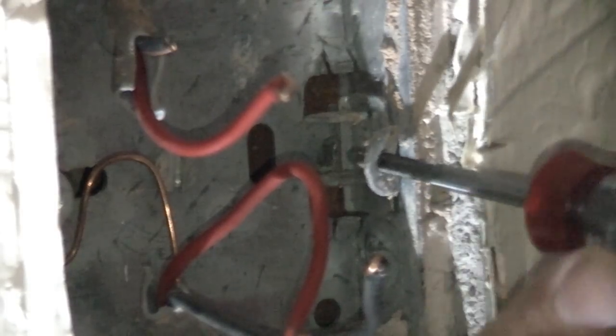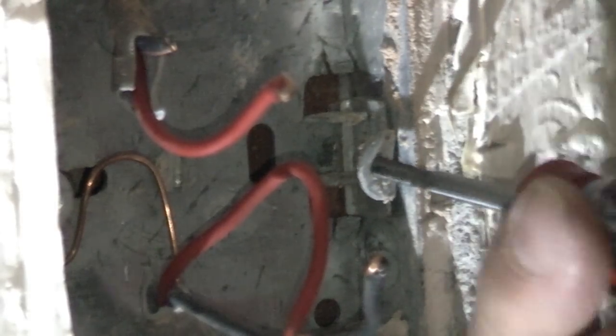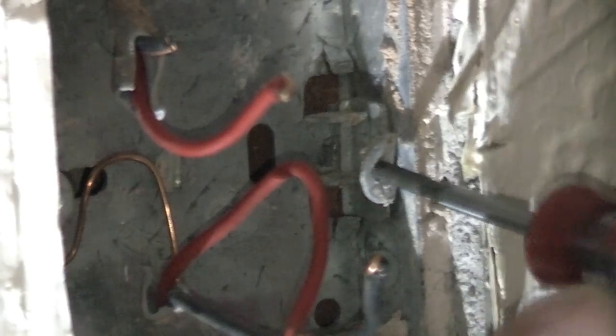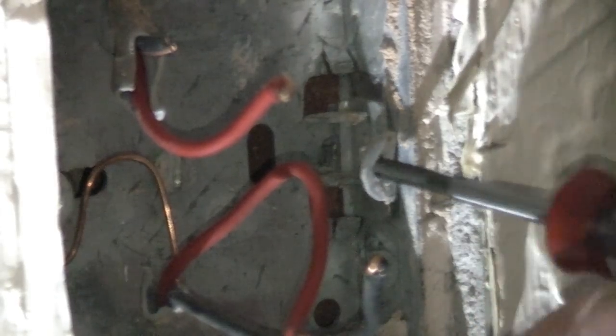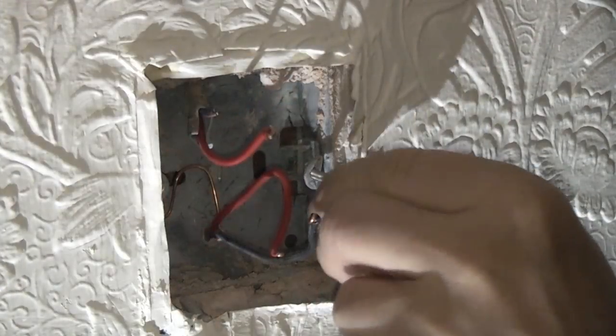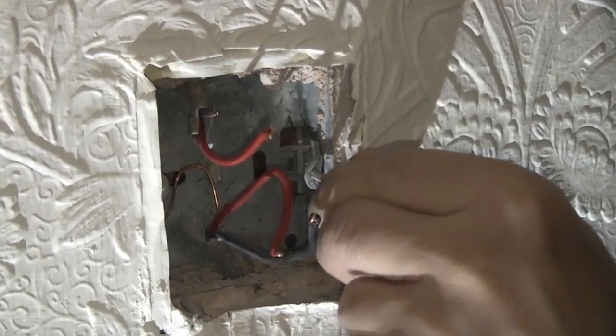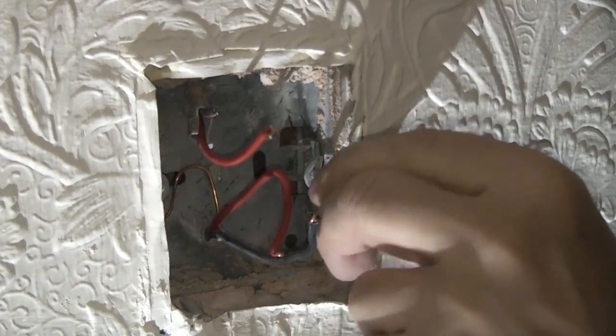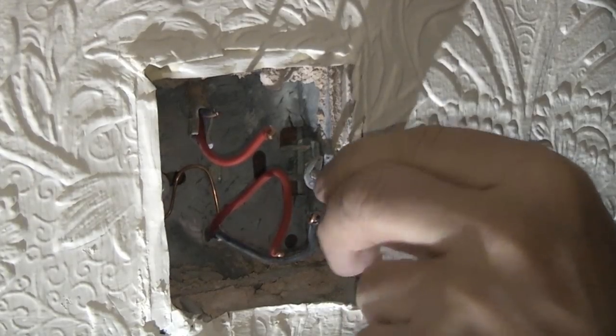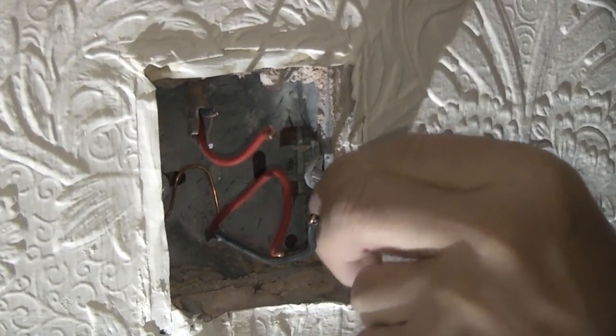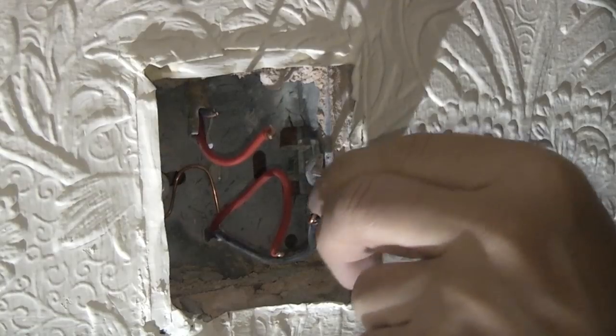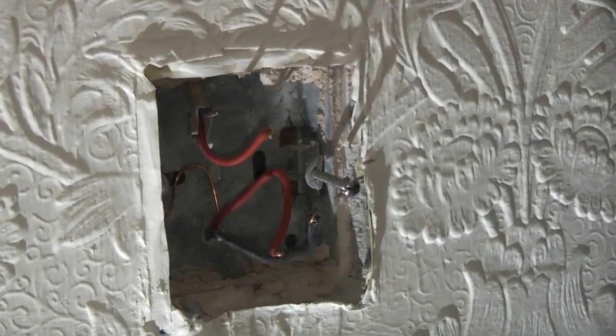Once you have removed the screw like this it's important that you don't try and use it again in case it strips the lug again. So it's always a good idea to get a brand new screw. In the UK screws for sockets and switches are always M3.5.